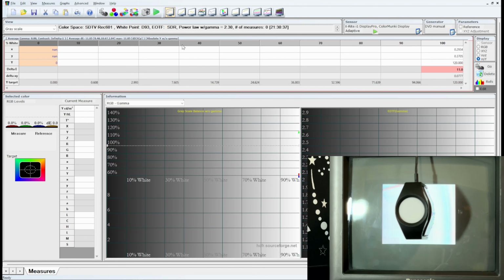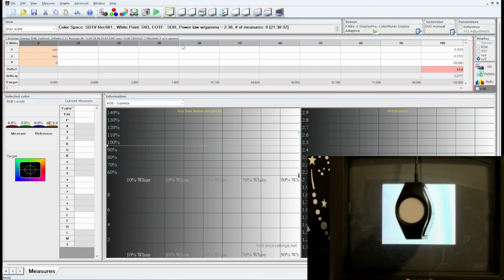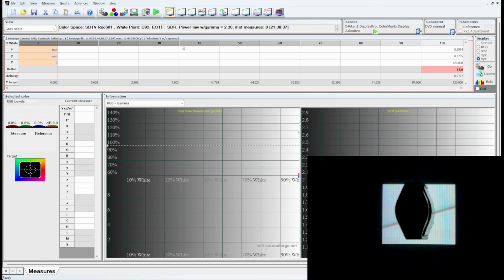Now that we have this set up, we want to turn off our lights. You want to do this in as dark of a room as possible. If you have blackout curtains or a basement with no windows, you'll want to do your calibration there. Or if you have to do it in a room with windows, you'll want to wait until nighttime and turn off all of your lights. So I'm going to turn off my light. Now we are in a pitch black room.